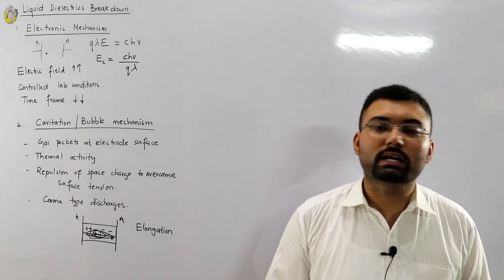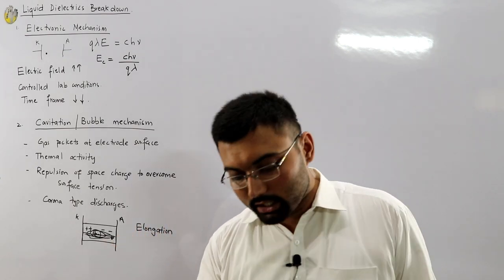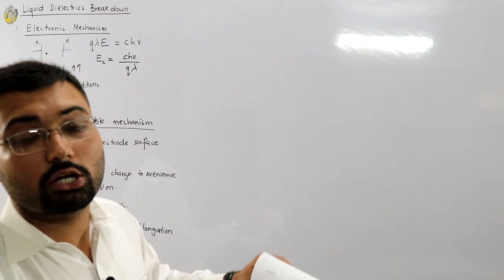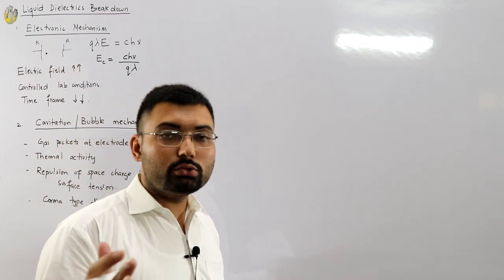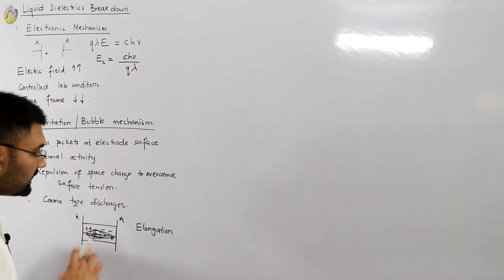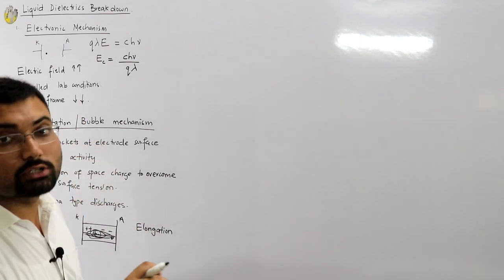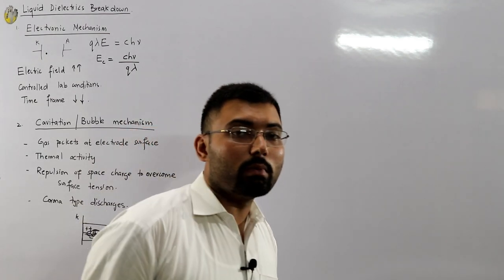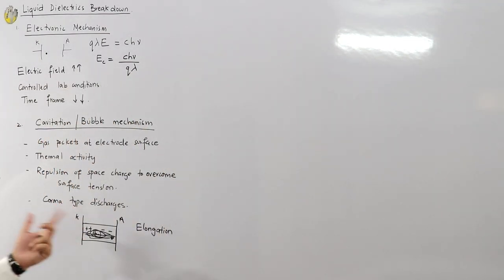To summarize: the bubble is present, it elongates, it cannot physically move but it elongates further, more charges accumulate, it elongates even further, and eventually bridges the electrodes — a short circuit path. The current flows through the bubble material because the liquid has high dielectric strength whereas the bubble has low dielectric strength.